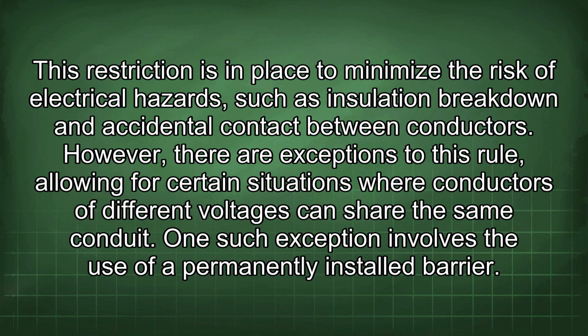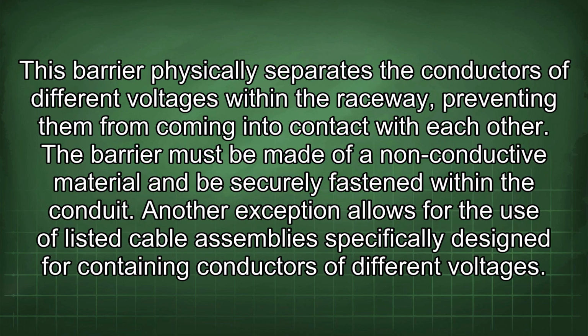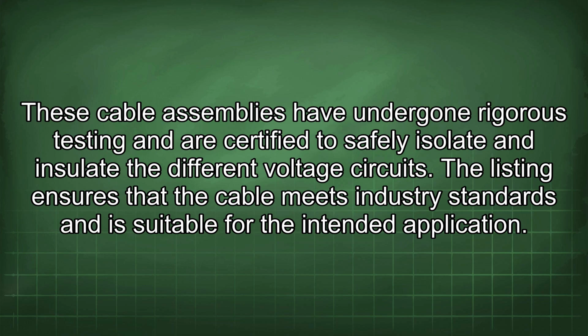conductors. However, there are exceptions to this rule, allowing for certain situations where conductors of different voltages can share the same conduit. One such exception involves the use of a permanently installed barrier. This barrier physically separates the conductors of different voltages within the raceway, preventing them from coming into contact with each other. The barrier must be made of a non-conductive material and be securely fastened within the conduit. Another exception allows for the use of listed cable assemblies specifically designed for containing conductors of different voltages. These cable assemblies have undergone rigorous testing and are certified to safely isolate and insulate the different voltage circuits. The listing ensures that the cable meets industry standards and is suitable for the intended application.